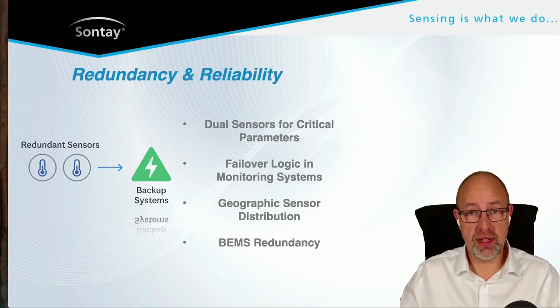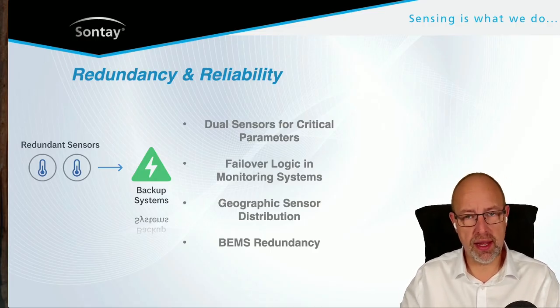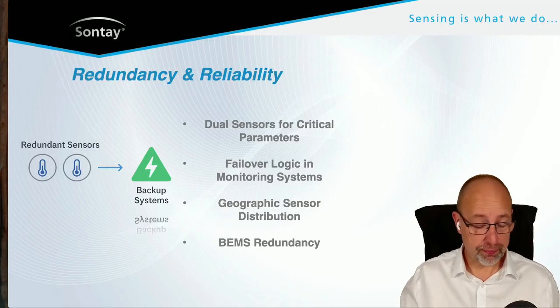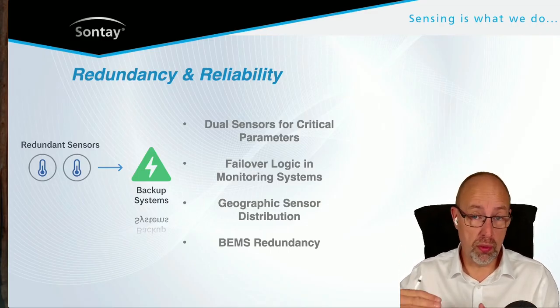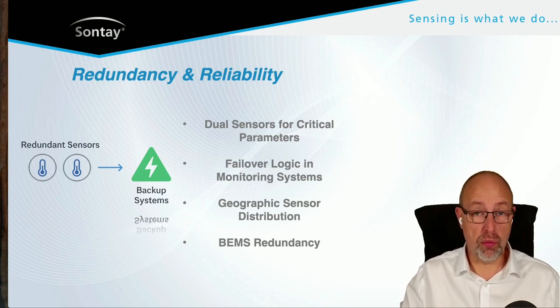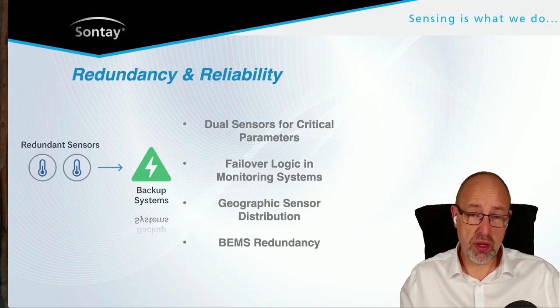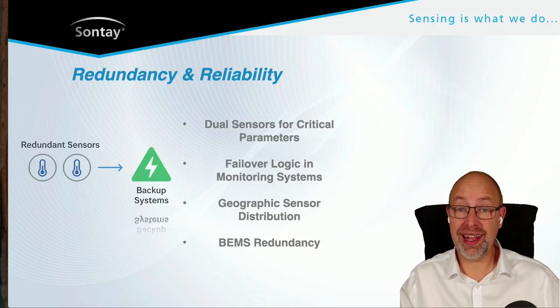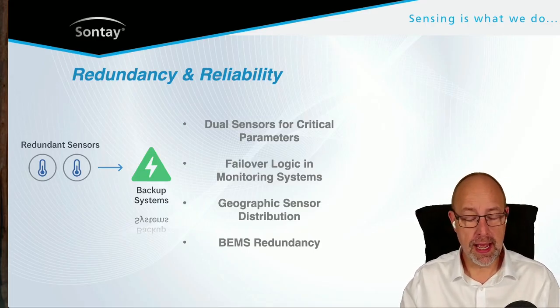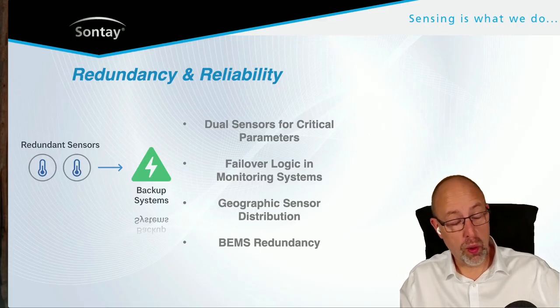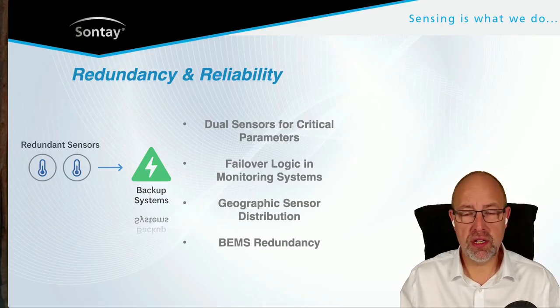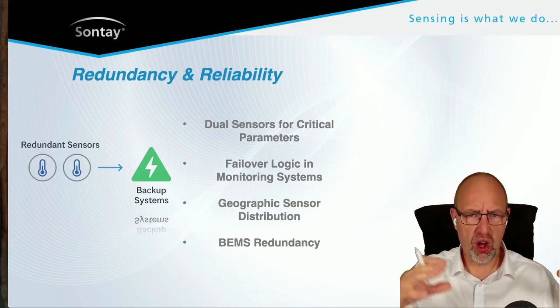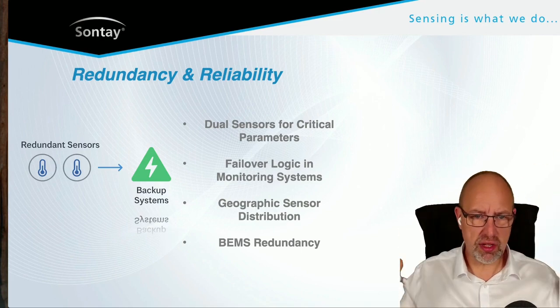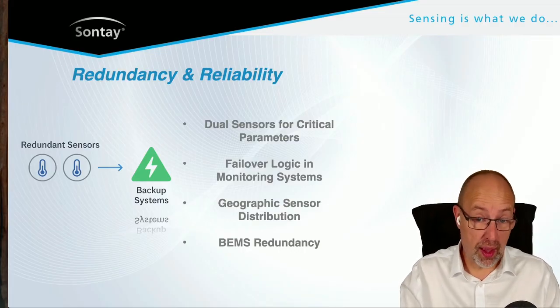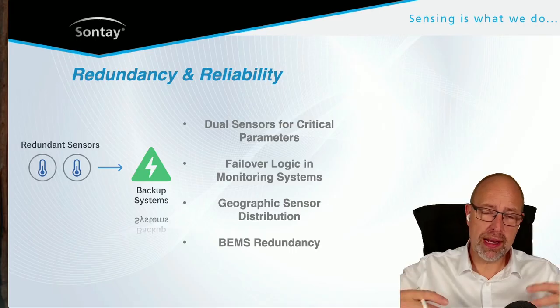You need to understand what level of redundancy you need, and then what is a sensible way to implement that redundancy. If you have got 2 sensors and they are connected to different controllers in your BEMS network, that is usually enough to give you the redundancy you need. Part of that is if they're connected to different controllers, and you've taken the trouble to make sure the controllers are connected to different power supplies. I mentioned UPS power supplies in data centers. There's usually an A and a B UPS, so that you have redundant power. If you've got one controller connected to the A, one controller connected to the B, one sensor connected to the A controller, one to the B controller, then you've duplicated your data adequately. You don't need to do all this stuff with changing the I/O modules so that one of the B modules can work with an A module, etc. So having dual sensors is about having the sensors but also connecting them to the right place, and how you manage that data when it comes in as well.